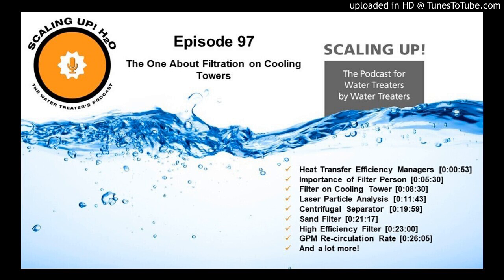It's something you need to look at, because if your laterals are broken, you're liable to get media flowing through your filter and out down the drain, potentially even into the cooling tower. So it's important that the laterals be inspected and that they're okay, which is why I generally use stainless steel. I don't use plastic anymore. That's a great tip. Now, I've worked with people that say, regardless of what the manufacturer says, and some manufacturers say all you have to do is go back with the sand media, regardless of that, you should put some sort of support media down in there first. What are your feelings on that?